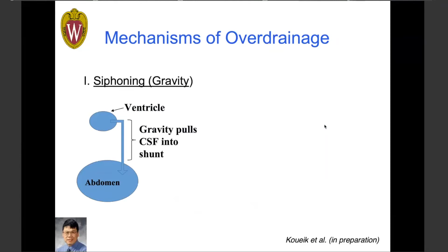For example, if you were to cough, the ICP in your head could go up to 50. Well, the highest pressure valve on the market is 20, maybe 40 if you look at the Certas, virtual off. So fluid's going to go through the shunt. It's not going to go through the shunt only when the average ICP reaches a certain level. It's going to go into the shunt every time you have an instantaneous cough, sneeze, bowel movement, running up the stairs, running down the stairs, or cardiac pulsations. Every systolic pulse way exceeds the opening pressure of a valve, which means that by definition, that valve is constantly open. It doesn't open and close like the companies feel.